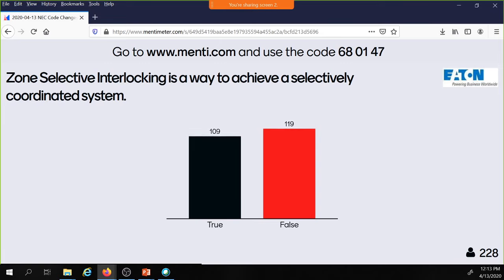If you have an overlap in the overload region, they will trip. The upstream could go before the downstream on overload. If you have a misprogrammed short time delay region, the upstream breaker could trip before the downstream breaker on short time delay. And if the fault current is greater than the instantaneous pickup of both of those devices, they could both open. Absolutely. Zone selective interlocking or not. You have to make sure you understand ZSI is there to act when a fault occurs in between those devices. And that is the only time and the only benefit you get from zone selective interlocking, which is a huge benefit to preserve the safety of the equipment.